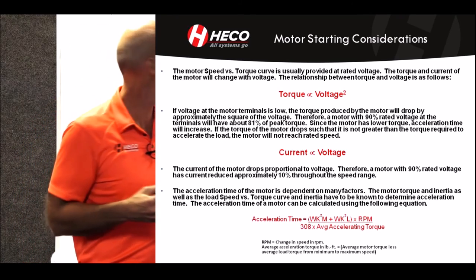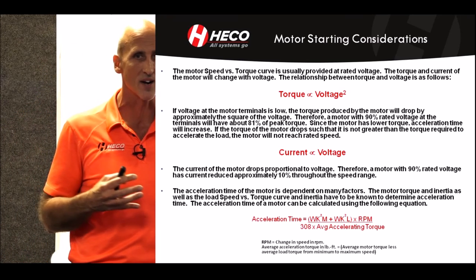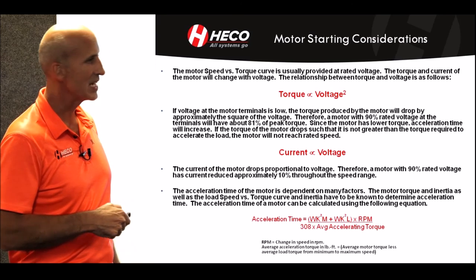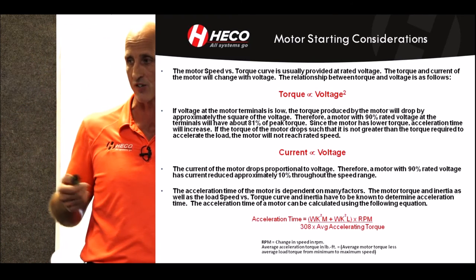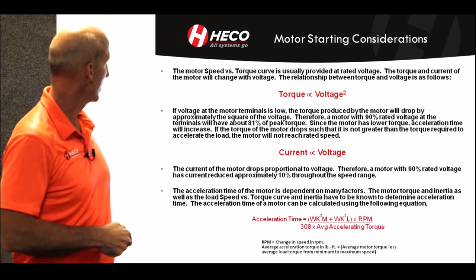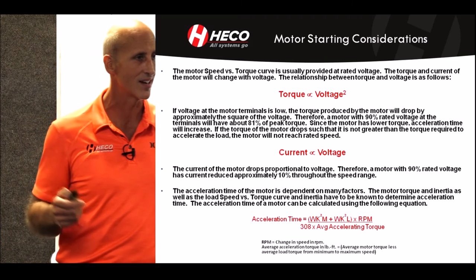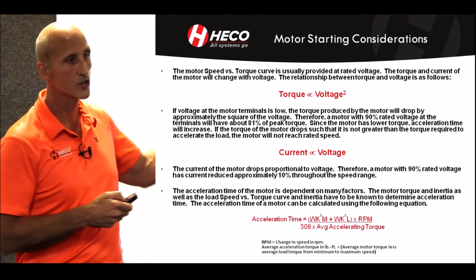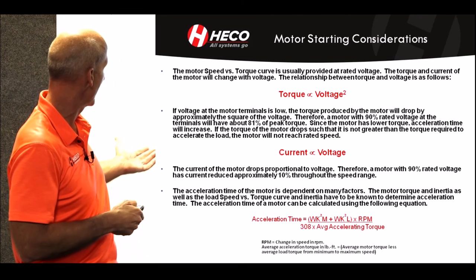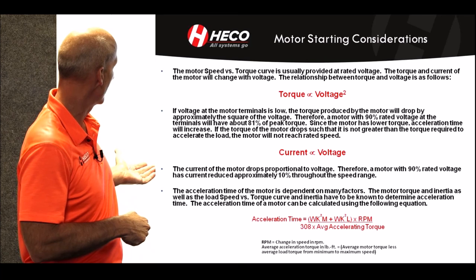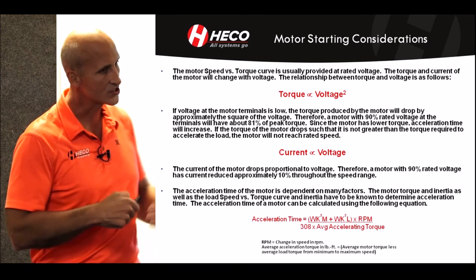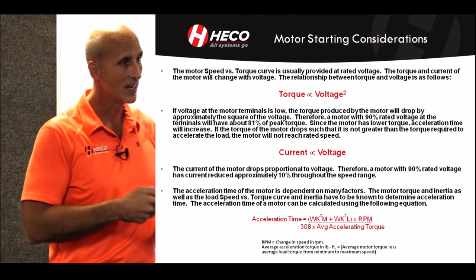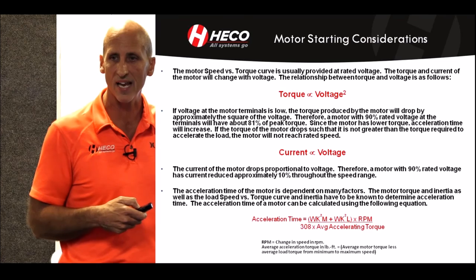Motor starting considerations: torque is proportional to voltage squared. If your voltage is only 90% of rated, which is typical—especially on start—you're going to have only about 81% torque available, because it's the square of the voltage difference that impacts the torque. Current is proportional to the voltage. The acceleration time of the motor can be calculated with the formula: acceleration is dependent upon the inertia of the load, the inertia of the rotor, the two combined, and the voltage applied—determining how long the motor takes to come up to speed.